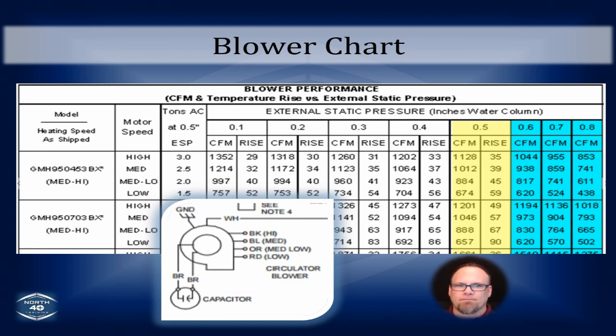If you don't do that, what happens? If you don't set up your blower speed properly, well, then what? To be honest with you, I went over a decade not understanding any of this stuff. So what happens to those air conditioning systems? Well, almost everyone that comes from the manufacturer has high speed as your air conditioning speed. If high speed is your air conditioning speed, and that's way more CFM or airflow than what the system actually needs, it makes your coil too warm. It takes the cool away from your coil too quickly, so you don't get good dehumidification, you don't get a good air temperature drop across that coil.